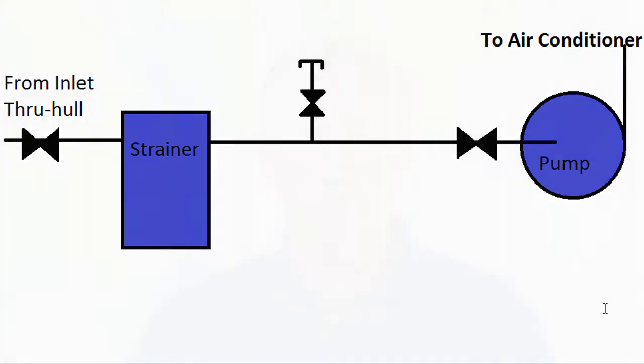I like to do it about once a month. If you don't have a T already installed, I recommend looking at it. The best thing you can do is have some way that if anything gets caught in the system, you can blow it back out. All right, so the important things that we have in this system are the strainer, the seacock, and the pump. And the most important thing to do is to keep the system clear of obstructions. Most times that you have a problem with your marine air conditioning unit, it's in the cooling water system. Keep that flowing and you'll keep the cold going. Thanks.